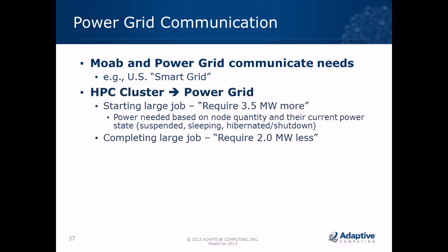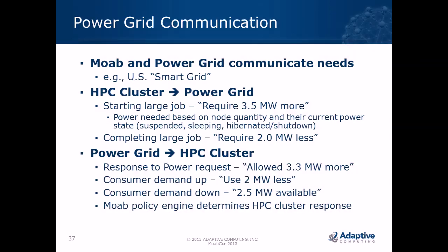The future vision is bidirectional communication with the power grid — the smart grid concept, already in use in some industries. For a very large HPC cluster needing to power up 10,000 nodes, that might require three additional megawatts; you'd need to communicate this demand to the power grid. Response time depends on the power generation source — a coal-powered plant takes up to an hour, natural gas a few seconds. Conversely, when completing a job, you notify the grid you're releasing power. The grid can also communicate back — for example, requesting you reduce usage by two megawatts during peak demand periods.